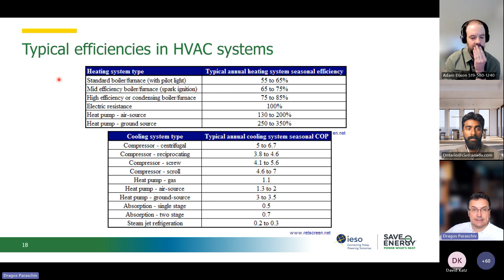Finally, I cannot skip discussing heat pumps, because they're such a fashionable project in many of our energy management initiatives nowadays. Typically we use heat pumps for two principal modes, heating and cooling, with the same equipment. Sometimes, because of the conditions in heating mode, we need a kind of third mode, the defrost cycle, to help the heat pump recover and continue providing heating in our building.